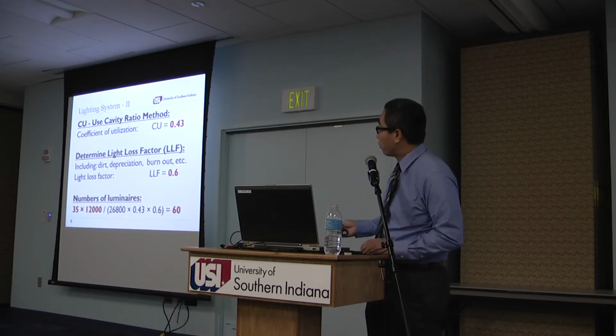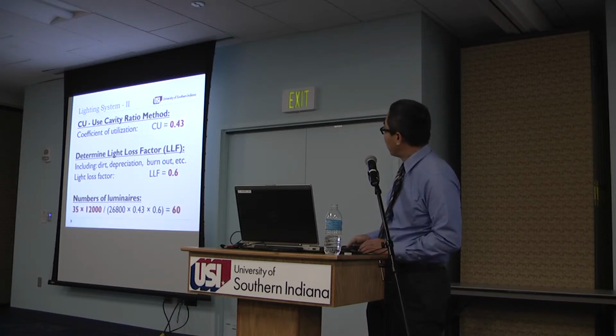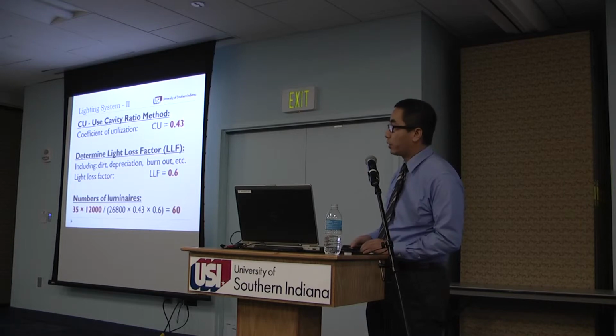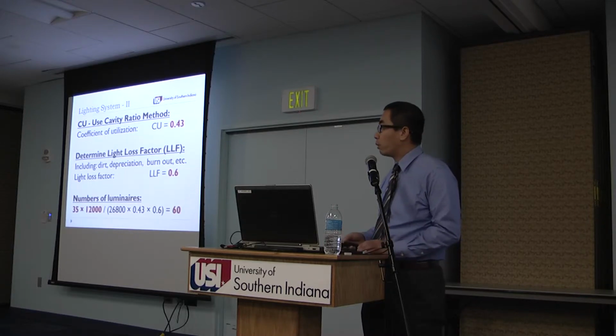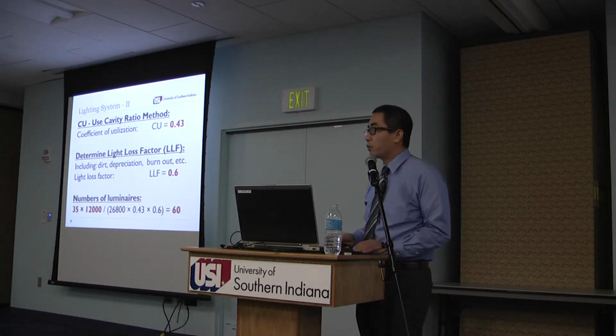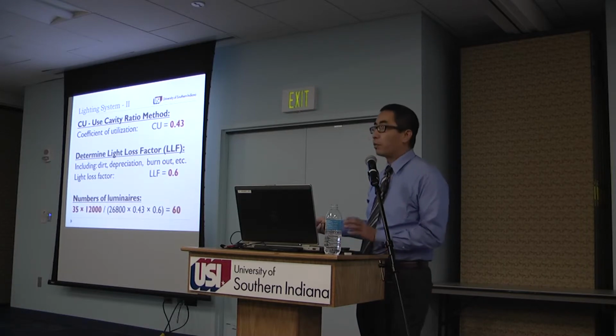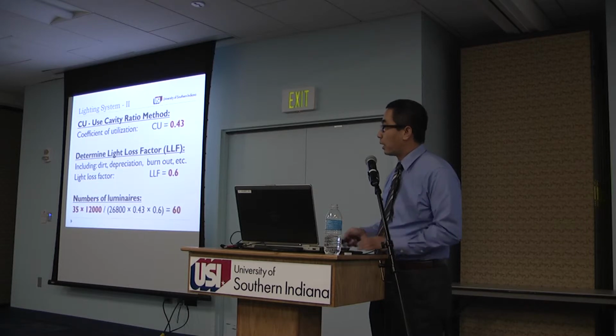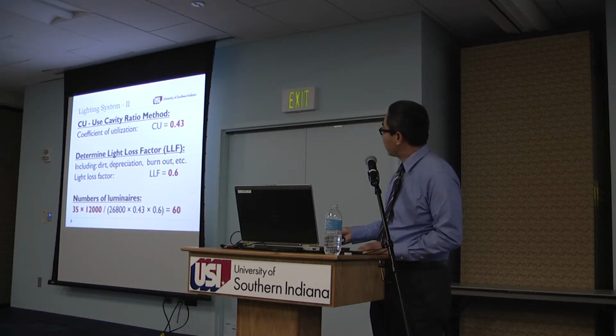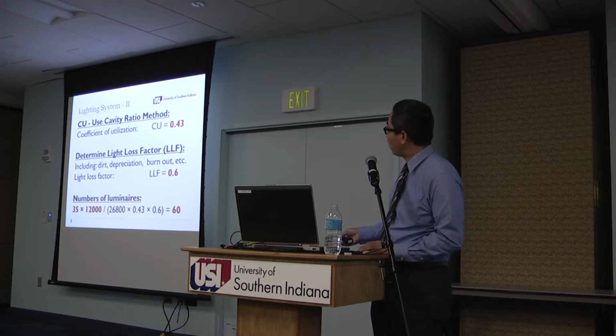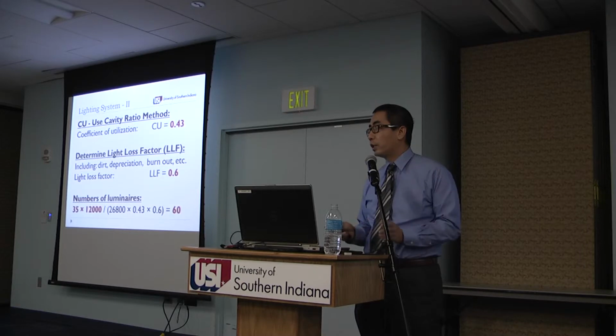And the lighting is going to deteriorate over time. Some of them burn out, and dirt will cover some of the lighting fixtures. So you apply another knockdown factor. That's 60%. And for this type of application, we need 35 foot-candles. That's the lighting level we need to do our preparation work. This room here, if you look at the surface here, probably gives you about 30 foot-candles. That's the lighting level we're looking for. Based on the lighting fixture capacity, the level we need, the square footage of the space, and the knockdown factors on the fixture output, we can calculate how many lighting fixtures we need in the whole building.